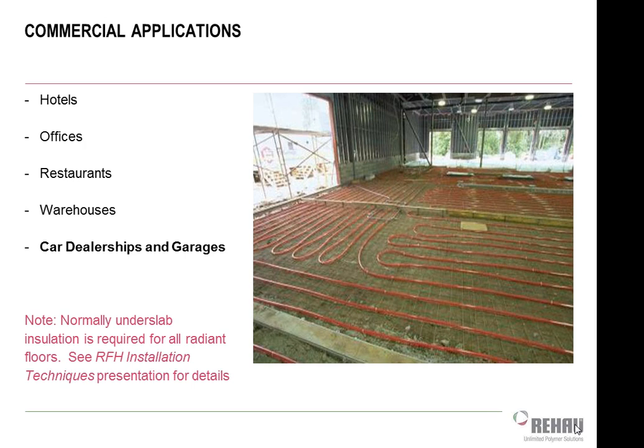But if you have a radiant-based system, whether it's radiant tubing in the floor or an infrared heater from above, you're not heating the air. You're heating all the objects. So you're heating the floor, the ceiling, the walls, the racking, the forklifts, the people. So warehouses, especially high-volume door warehouses, may choose to use a radiant-based system.